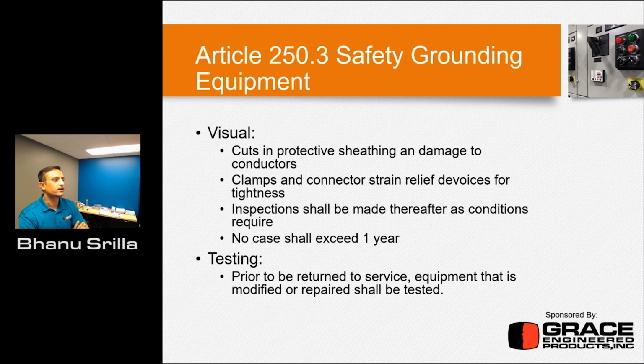And Article 250.3 talks about the safety grounding equipment. So you need to make sure you do the visual and also testing. Visual includes checking for cuts in the protective sheathing and damage to conductors. You need to make sure the clamps and the strain relief of those devices are checked for tightness, and the inspection shall be made thereafter as condition requires.